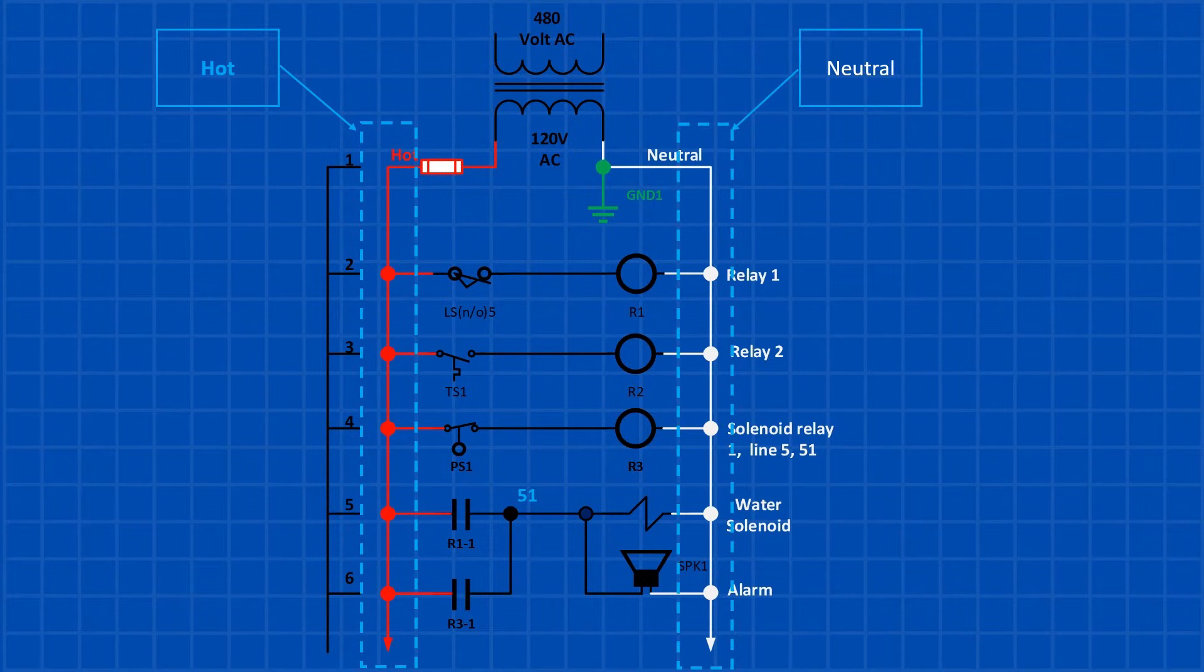Now, let's look at other important elements of the ladder diagram. Input and output devices are wired between the hot and neutral lines. Output devices always appear on the right side of the ladder diagram, with one side directly or indirectly connected to the neutral.